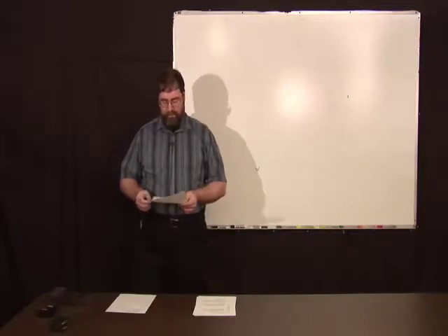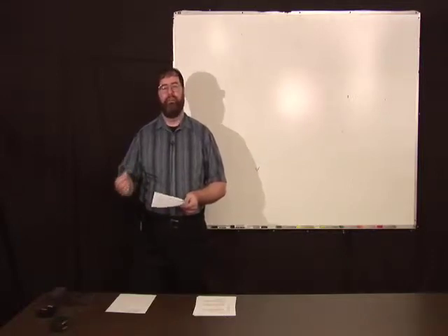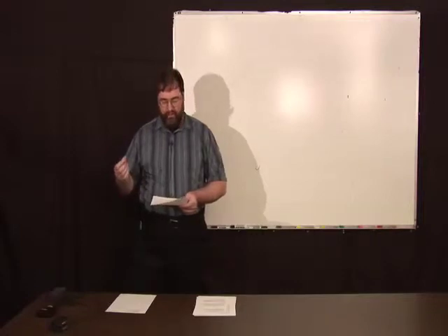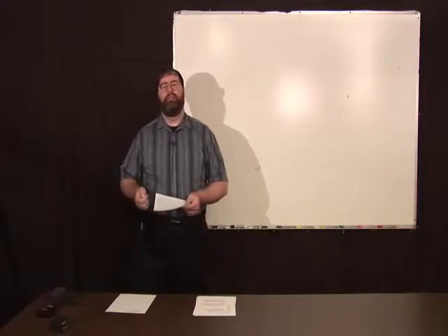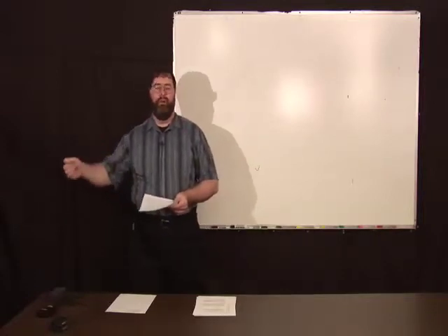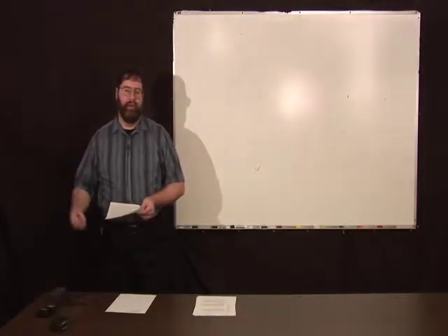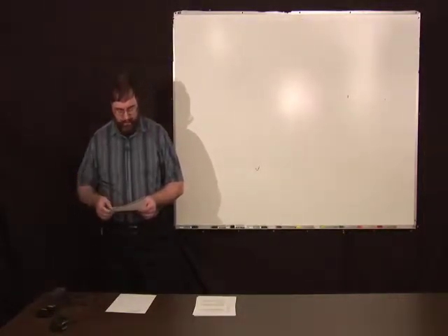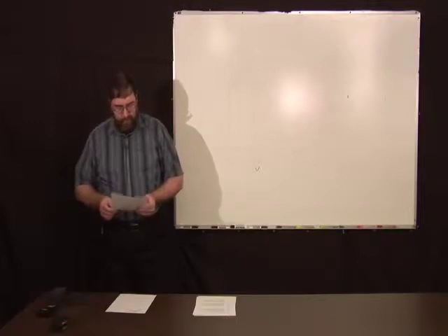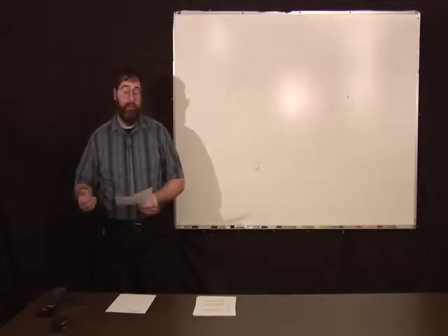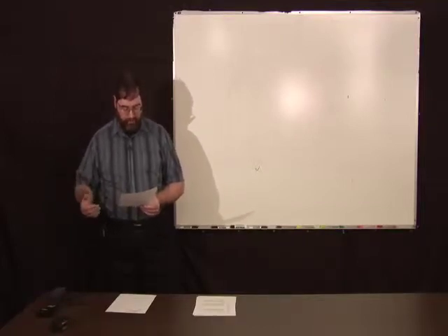Another thing is each intercomparison, there's an unbroken chain of comparisons, all having stated uncertainties. Each step along the way, an uncertainty analysis has to be made back to the national or international standards. For a traceable measurement, the result has to have several things.